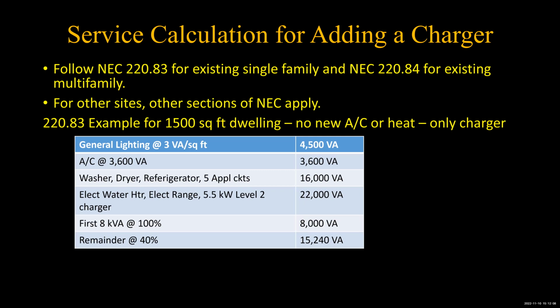Let's say that it's about a 3-ton air conditioner, and that's about 3,600 volt amps. General lighting is 3 volt amps per square foot. Any EEs have done this calculation over and over again. For the non-EEs, this is all coming straight out of the rule book, the National Electrical Code. And again, this is the number you get.